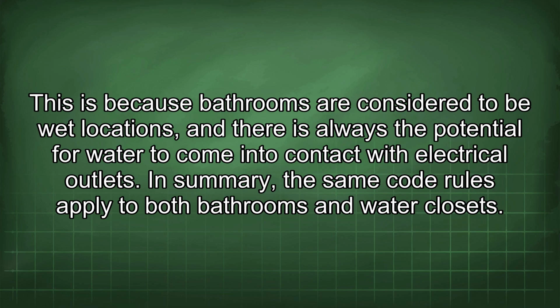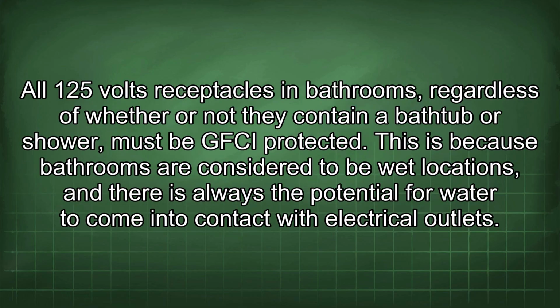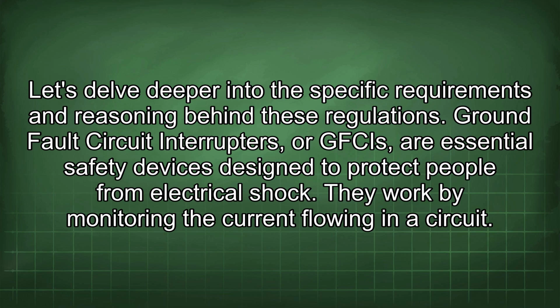This is because bathrooms are considered to be wet locations, and there is always the potential for water to come into contact with electrical outlets. In summary, the same code rules apply to both bathrooms and water closets. All 125 volts receptacles in bathrooms, regardless of whether or not they contain a bathtub or shower, must be GFCI protected. This is because bathrooms are considered to be wet locations. Let's delve deeper into the specific requirements and reasoning behind these regulations.